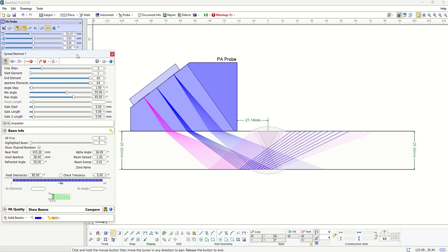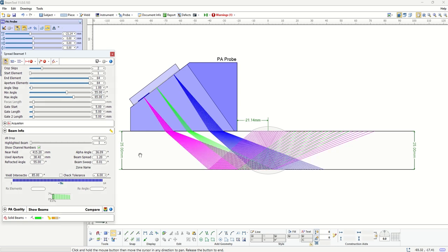The difference between the compound scan and sectorial scan is that in the case of sectorial scan, all the beams that we choose will be generated by the same aperture. But when we go to compound scan, we can choose our different angles to be generated by different apertures. For instance, here, in my compound scan, I'm just going to change the color to green so you can see it easier. I go to the same min and max angle, 50 and 70. But then you'll notice that in terms of options, I have the option to choose the first element and end element, which in this case I chose 64, which is the last element of the probe. And then we can choose aperture element size.